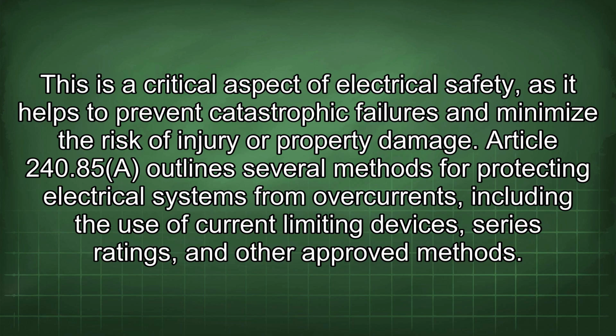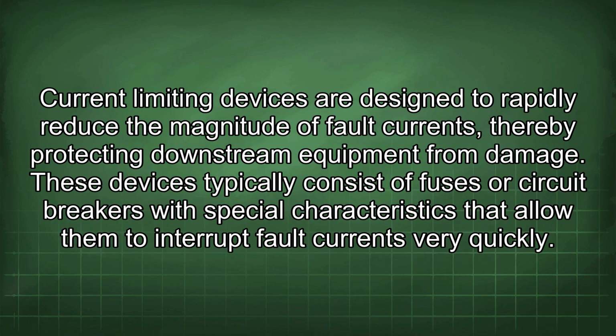injury or property damage. Article 240.85 outlines several methods for protecting electrical systems from overcurrents, including the use of current-limiting devices, series ratings, and other approved methods. Current-limiting devices are designed to rapidly reduce the magnitude of fault currents, thereby protecting downstream equipment from damage. These devices typically consist of fuses or circuit breakers with special characteristics that allow them to interrupt fault currents very quickly.